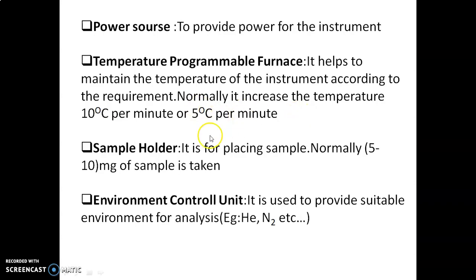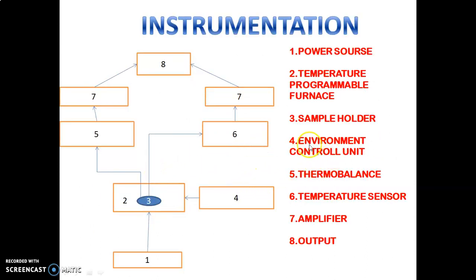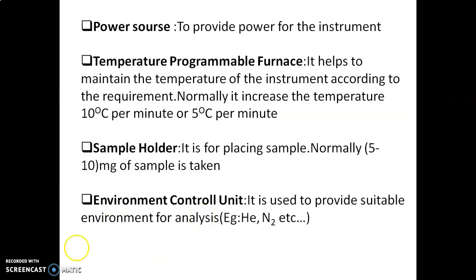The third part is the sample holder, which holds the sample. Normally we take five to ten milligrams of sample. The fourth component is the environment controller unit, which controls the environment. Some experiments are carried out in an inert atmosphere, in the presence of oxygen, or in air. The environment controller unit provides the suitable environment required for analysis — helium, neon, or whatever is needed.